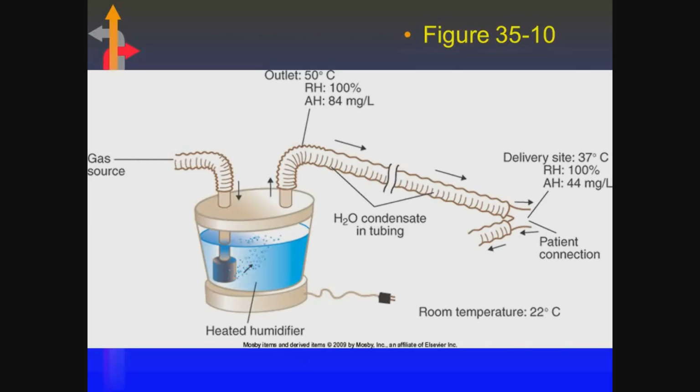And you've got to be careful of the condensate. Again, I may have 100% relative humidity at the outlet, but by the time it goes through the room to the patient, it cools enough that you collect condensate in the process. And part of the problem is I've got all this water. Let me get my, wrong one. Got to have blue for water.